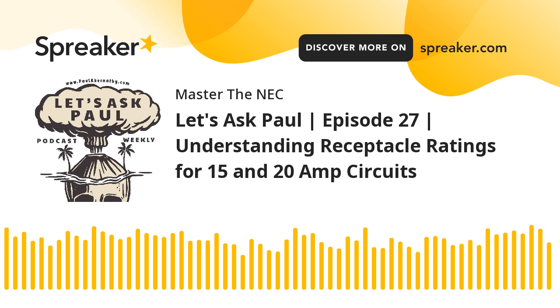Now let's talk about, since you brought up 15 and 20 amp rated circuits, receptacle branch circuits are generally going to be 20 amp rated for things like laundry areas, bathrooms, garages, kitchens, of course, except for the individual branch circuit going to, let's say, a refrigerator, which could be 15 amperes or greater, but that's an individual branch circuit. But the small appliance branch circuits are typically going to be 20 amps. Your dining rooms, your parlors, your breakfast rooms, and similar, they're going to be 20 amp branch circuits. Of course, the National Electrical Code tells us the minimum number of small appliance branch circuits, with a minimum of 2. You could have more than that. But everything else throughout the dwelling that is not associated with those things that are stipulated as 20 amp circuits, they would be 15 amps.